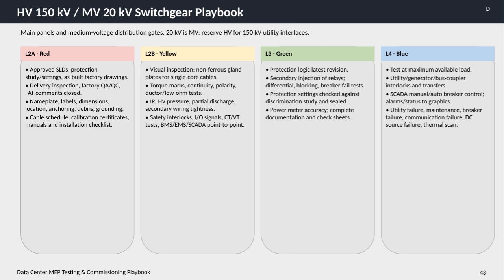This consists of verifying the latest protection logic revisions, performing secondary injections on relays, including differential, blocking, and breaker failure tests. We confirm the protection settings align with the discrimination study and are properly sealed. Accuracy of power meters is checked, alongside reviewing complete documentation and test check sheets.